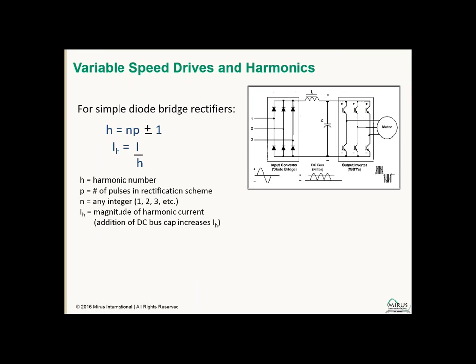So in our application today, the nonlinear load is a variable speed drive. Many of the applications out there where harmonics are an issue are associated with variable speed drives. The schematic shown here is a 6-pulse variable speed drive, which has a 3-phase diode rectifier on the input, which takes the AC power and converts it to DC. We might have a DC line reactor in the circuit, and DC bus capacitors to reduce the ripple on the DC, and then that DC voltage is applied to the inverter section, which is a set of IGBTs, which switch the DC at high speeds to simulate an AC waveform to deliver to the motor, and that simulated AC waveform can be created at varying frequencies, and that's how we would control the speed of the motor.